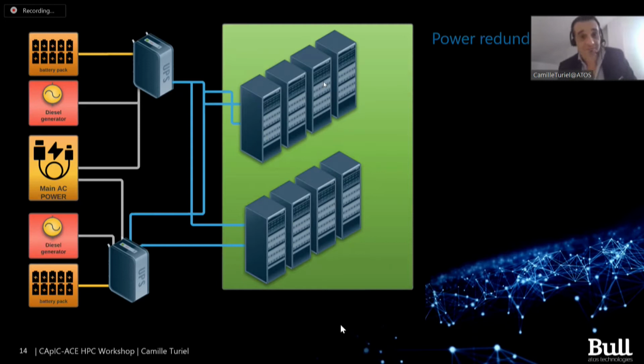So as you can see here, we have these racks represented, whatever the number. The idea is that you can see they are using redundant power, and that's why we said yesterday any single point of failure (SPOF) must be eliminated. We don't like a single point of failure, and as a system architect or designer, whatever your level, your goal is to eliminate every SPOF you can.